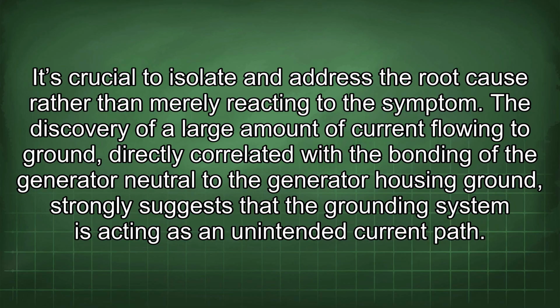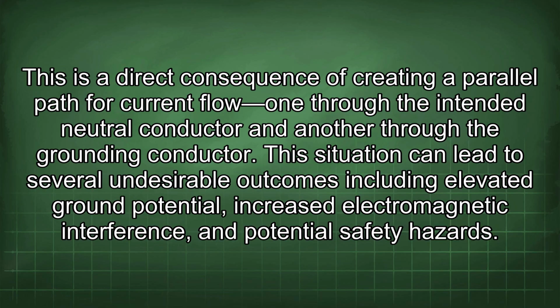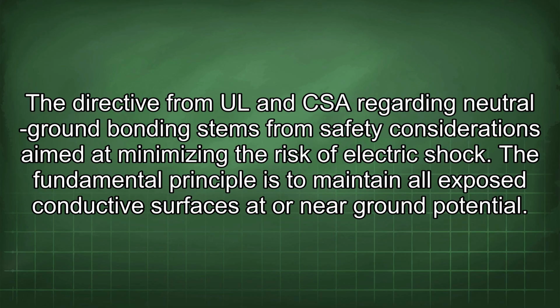The discovery of a large amount of current flowing to ground, directly correlated with the bonding of the generator neutral to the generator housing ground, strongly suggests that the grounding system is acting as an unintended current path. This is a direct consequence of creating a parallel path for current flow, one through the intended neutral conductor and another through the grounding conductor. This situation can lead to several undesirable outcomes, including elevated ground potential, increased electromagnetic interference, and potential safety hazard. The directive from UL and CSA regarding neutral ground bonding stems from safety considerations aimed at minimizing the risk of electric shock.